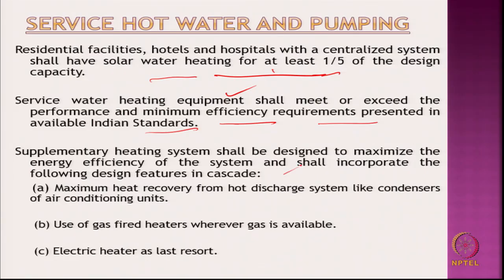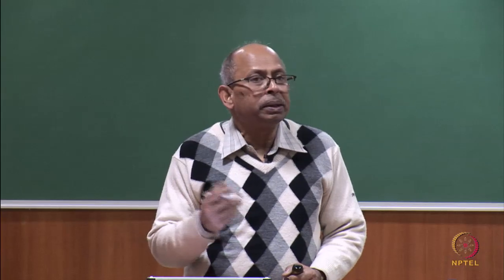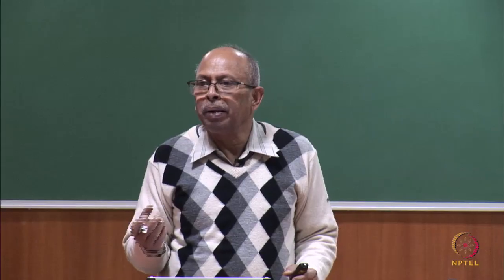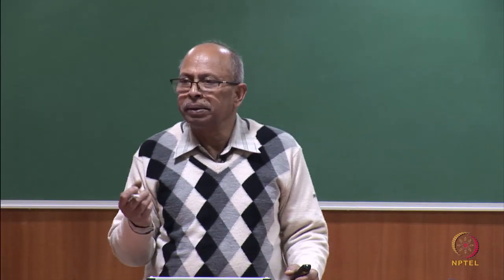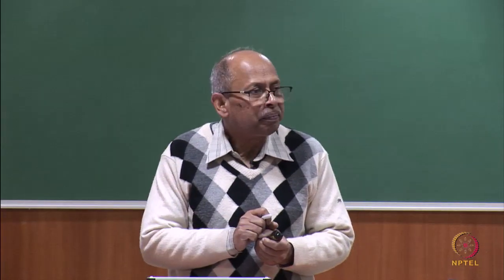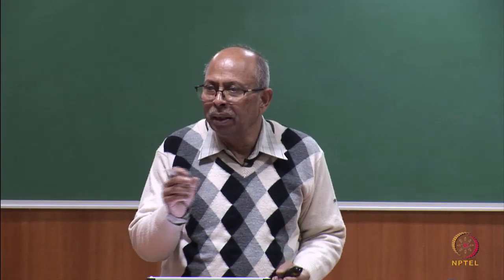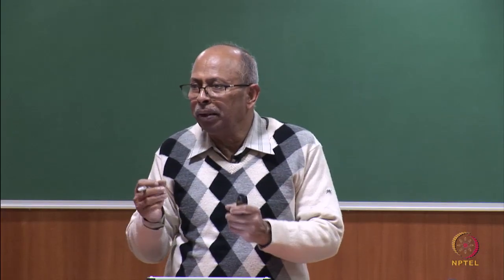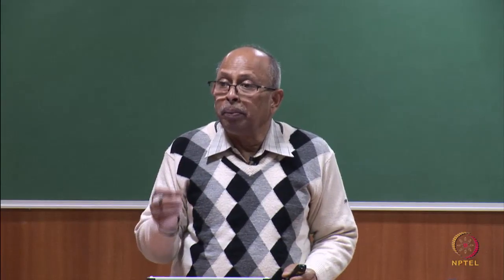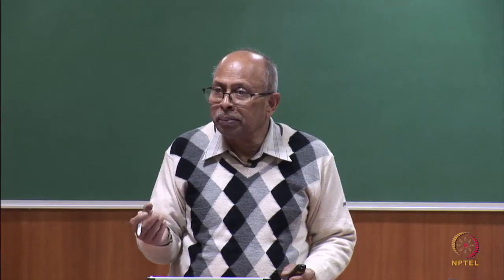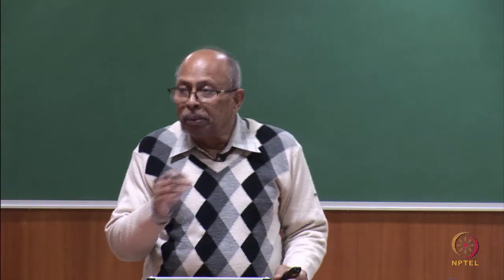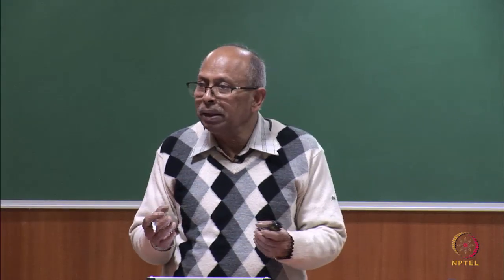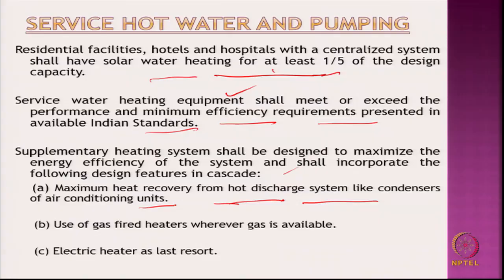Supplementary heating system shall be designed to maximize the energy efficiency of the system and shall incorporate the following design features: maximum heat recovery from hot discharge systems like condenser and air conditioning. So, as much heat recovery as possible, because in an air conditioning system, or if you just look at a refrigerator, what happens is the backside is warm, right. In a refrigeration system, the refrigerant is compressed and then it evaporates again in its cycle, and while evaporating it takes heat from the chamber, from wherever it is supposed to cool. But again it becomes vapor, and under pressure it becomes liquid again. So, when it becomes liquid, it will actually dissipate that energy. That energy, if you can recover it, it has to be recovered as much as possible. So, there should be a heat recovery system as well.